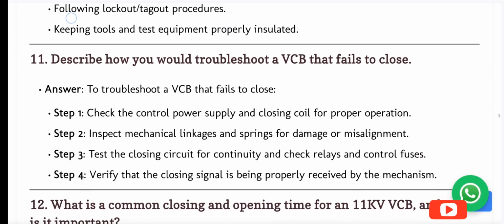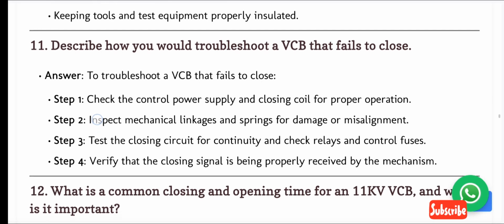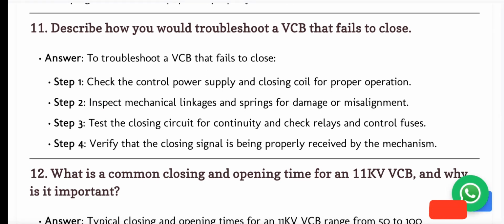11. Describe how you would troubleshoot a VCB that fails to close. Answer. To troubleshoot a VCB that fails to close. Step 1. Check the control power supply and closing coil for proper operation. Step 2. Inspect mechanical linkages and springs for damage or misalignment. Step 3. Test the closing circuit for continuity and check relays and control fuses. Step 4. Verify that the closing signal is being properly received by the mechanism.